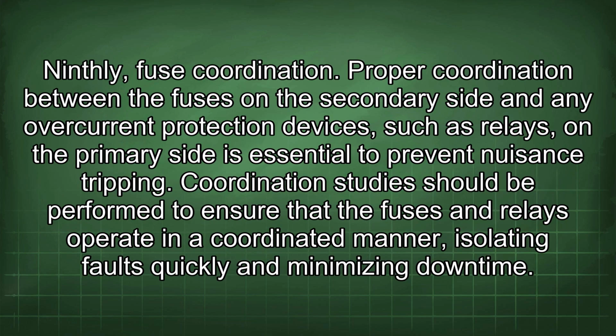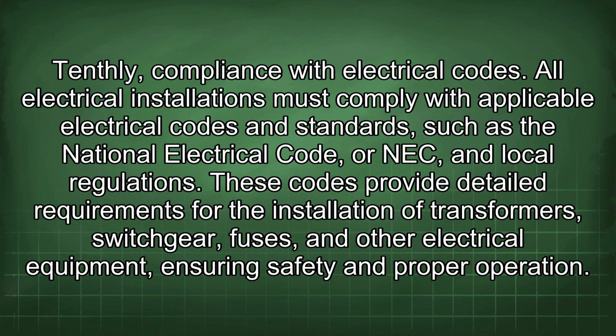Ninthly, fuse coordination. Proper coordination between the fuses on the secondary side and any overcurrent protection devices such as relays on the primary side is essential to prevent nuisance tripping. Coordination studies should be performed to ensure that the fuses and relays operate in a coordinated manner, isolating faults quickly and minimizing downtime. Tenthly, compliance with electrical codes.